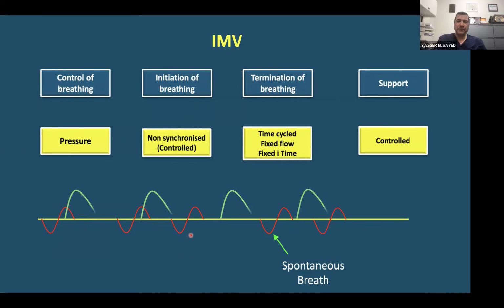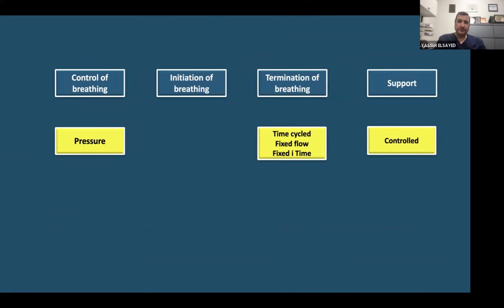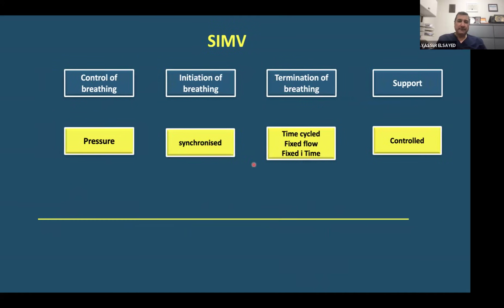There is no kind of synchronization in this mode. So for control of breathing by pressure, there is no synchronization. It is time cycled, fixed time, fixed flow, and fixed cycling between inspiration and expiration. It is totally controlled by the machine. There is no control from the patient. Now let us talk about the next one, SIMV. So with SIMV, we have the normal breaths again from the patient, negative for inspiration, positive for expiration. And the initiation of the breathing is through the machine.